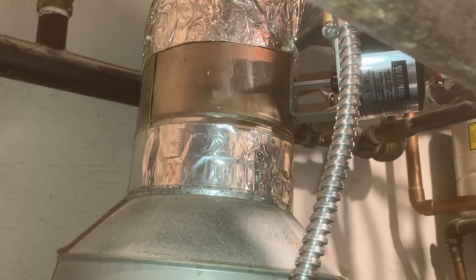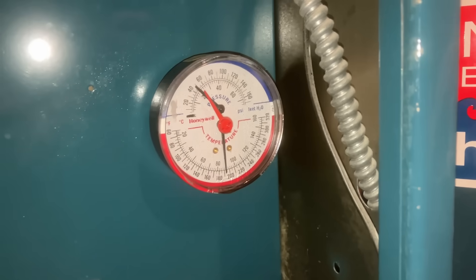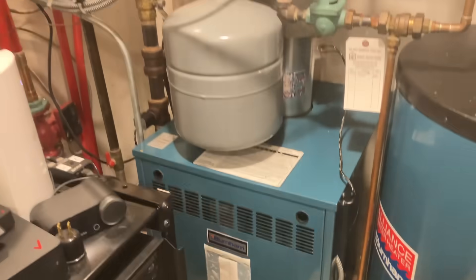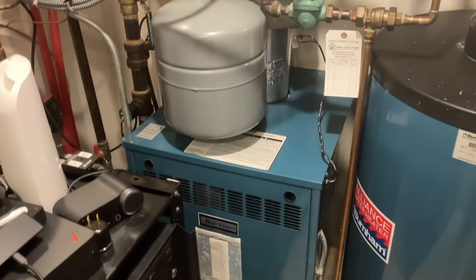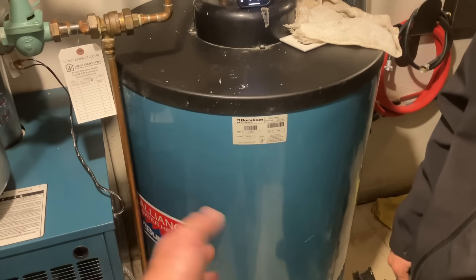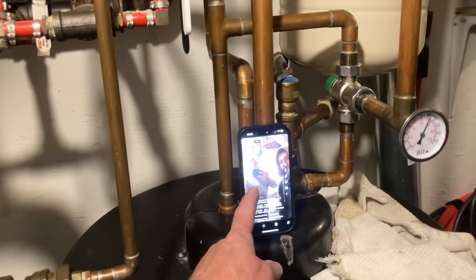Wait for it folks. The house is filled with Nest thermostats. The boiler is at temperature. We'll come back to that. I tasked Derek with doing a good cleaning of all the exterior components of this hydronic heating system. The customer also wanted us to do maintenance on the indirect water heater by Burnham — this is the 50 SL. This is a stone-line tank. This tank is heavy — very, very heavy.